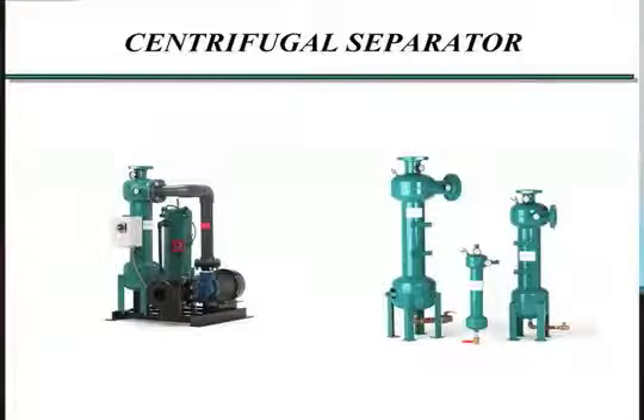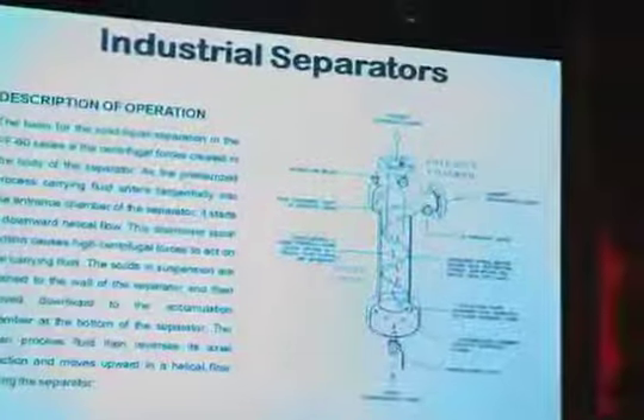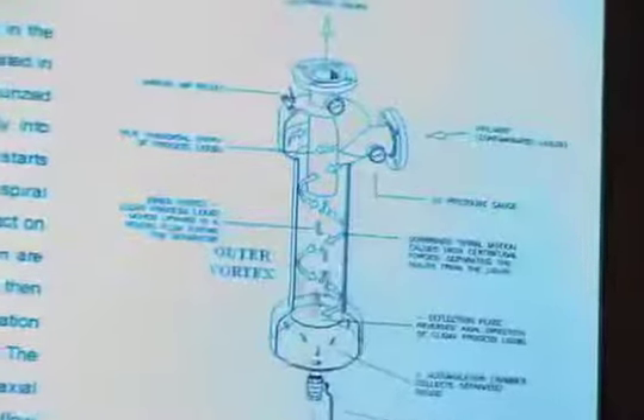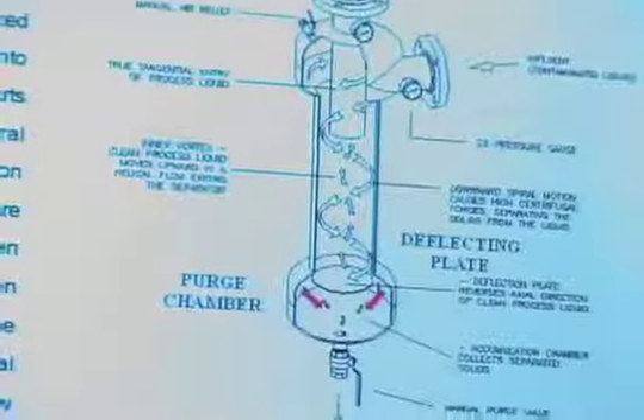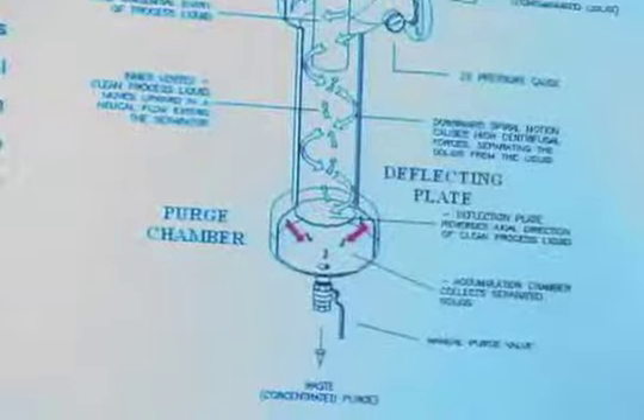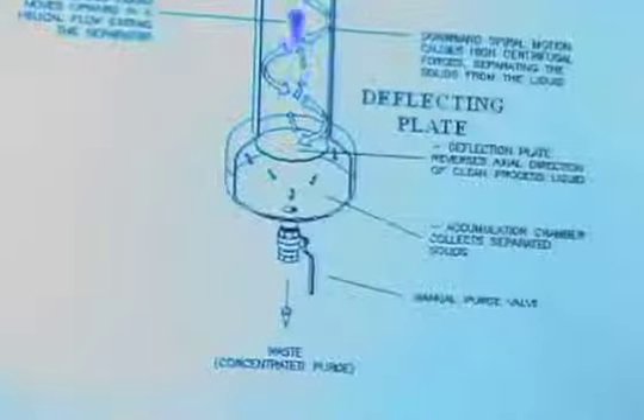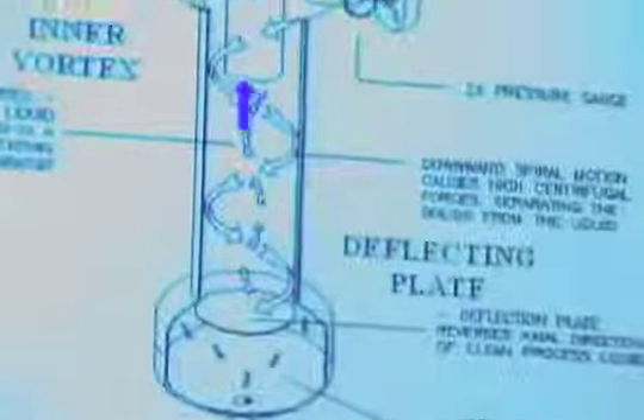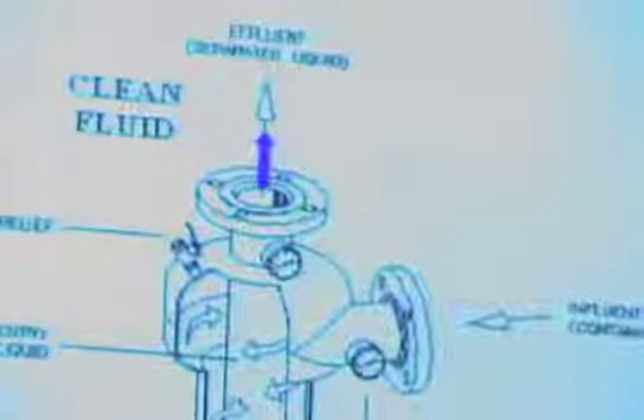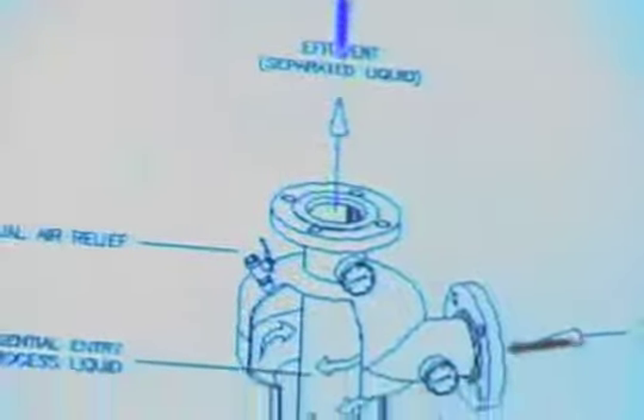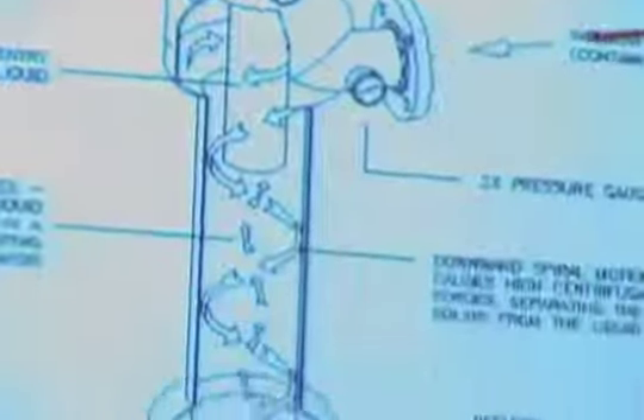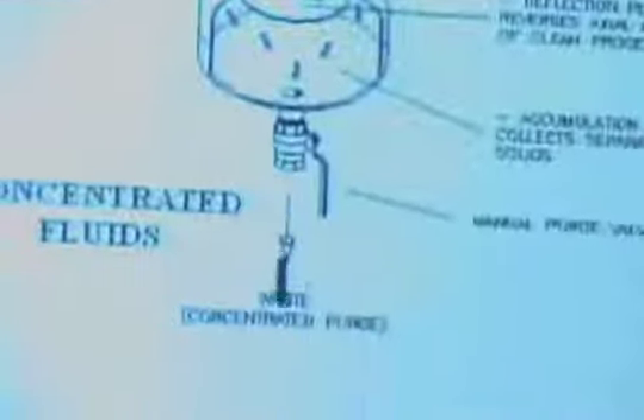The last type of filtration I'll talk about is a centrifugal separator. These are a little more complex device. They operate on the process of centripetal force. The water comes in through the top. It circles around at a very high rate of speed, throwing the particulates out. And then in a quiescent bottom chamber, the particulates fall out. And then the clean water runs back up through the center, back to your system. And then periodically, the bottom chamber is cleaned out by opening a valve. The water washes out and back to either the drain or, in some cases, a recovery vessel.